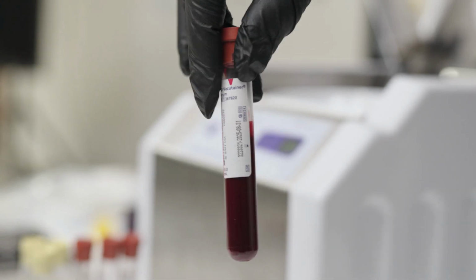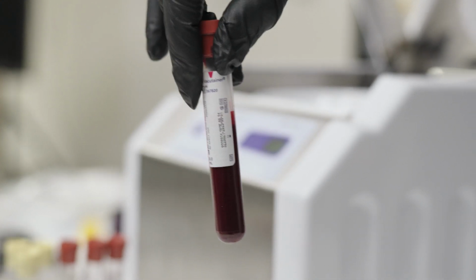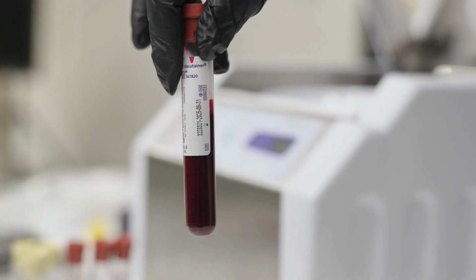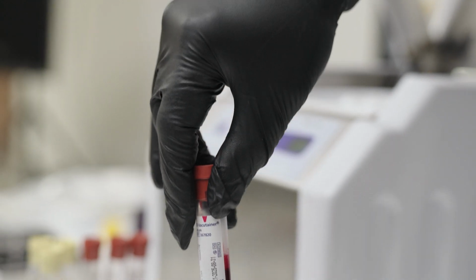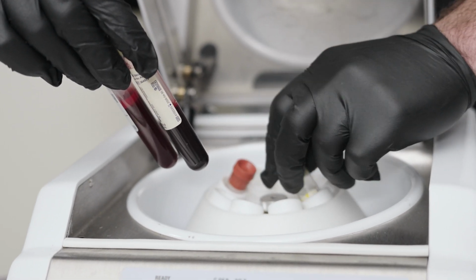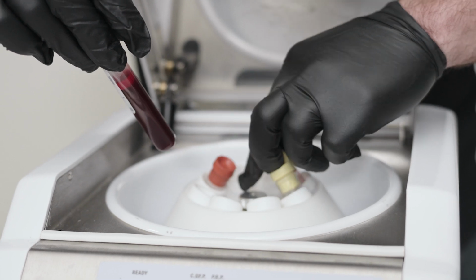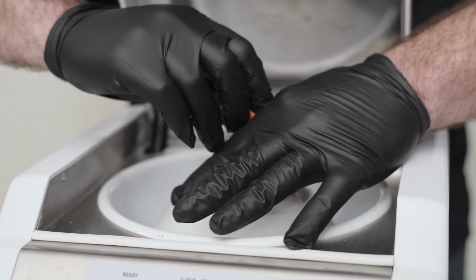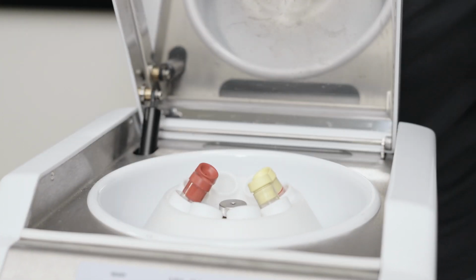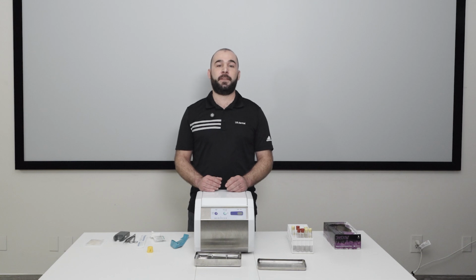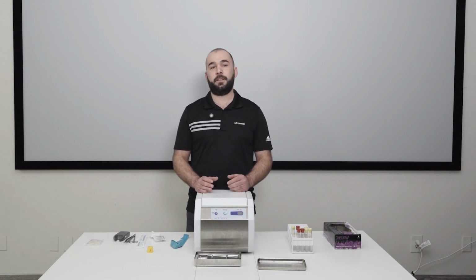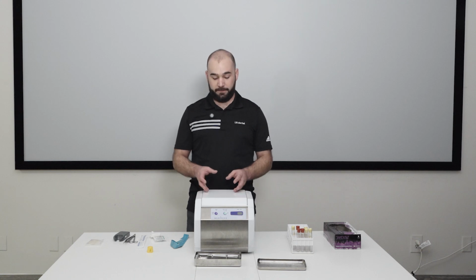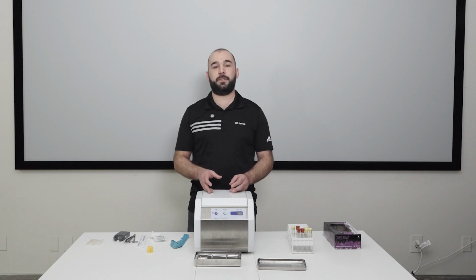Gently mix the blood with the activator in the red tube, but avoid shaking it too vigorously. Swirl it to mix it gently. Once the blood is collected, you'll place the tubes inside the centrifuge machine. It's important to counterbalance the tubes to ensure an even number of tubes inside the machine. If you have an odd number of tubes, you can add a tube with water in it to balance out the load. The Medifuge can hold up to 8 tubes.